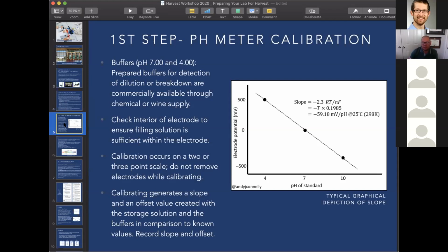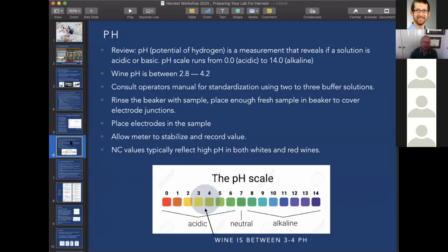pH probes should be calibrated at least once a week. You can calibrate them before the measurement as well, or you can just calibrate once a week, record the calibration data, and then go back to it the following week and calibrate again and record that data. I like to just keep it on a pad, or I just stick it right on the pH probe, that we've calibrated, we're good to go, and we are within the benchmark ranges for our winery.